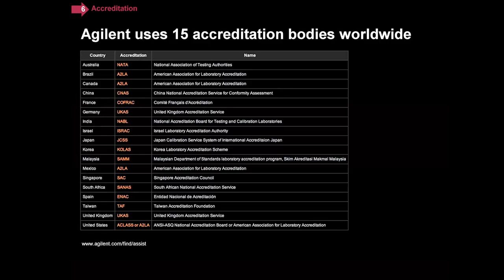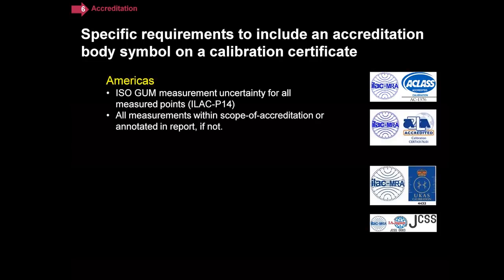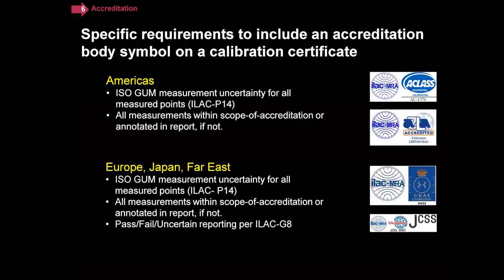Sometimes I get asked: are there specific requirements when you want the accreditation body logo on a calibration certificate? And there are. In the Americas, you have to provide the measurement uncertainty — this is according to ILAC P14 — and all measurements must be within the scope, or if they're not, you have to report it. In other regions — Europe, Japan, and the Far East — those first two conditions are the same, and most accreditation bodies there also ask you to do your pass-fail reporting according to ILAC G8. We have specific services targeted at that, so if that's what you need, that's what you can get.